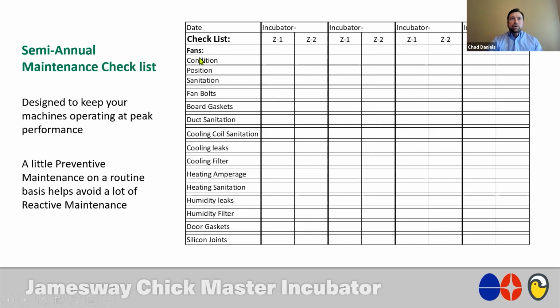And I'm going to go into a little bit more detail around these items associated with the fan, simply because of my statement earlier in saying that it's the heart of the machine. As we go down the list, oftentimes we see issues around fan bolts that hold not only the motor mount bracket into place on a wooden fan board, but the bolts on a Vosterman kit as well, and even the fan guard itself. Oftentimes we see those wear down. So it's good to have that on your checklist.